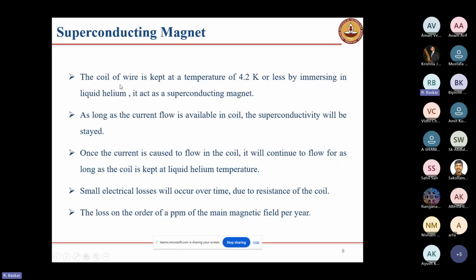The coil of wire is kept at a temperature of 4.2 Kelvin or less, by immersing it in liquid helium, and it acts as a superconducting magnet. As long as current flow is available in the coil, the superconductivity will stay. Once the current is caused to flow in the coil, it will continue to flow for as long as the coil is kept at liquid helium temperature. A small electrical loss will occur over time due to the resistance of the coil. This loss is in the order of ppm per year, so we don't mind those things.